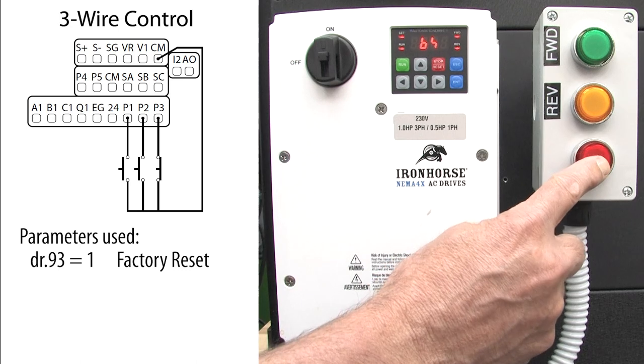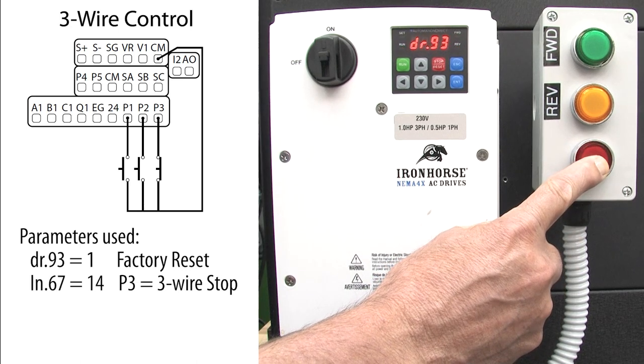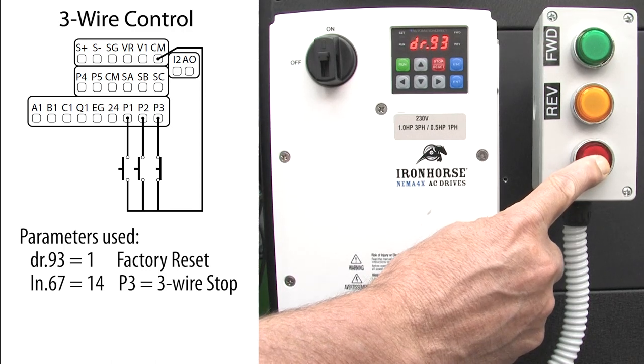If I press that normally closed switch to open it, the drive stops blocking the output. So, let's change digital input P3 to be the 3-wire stop input.